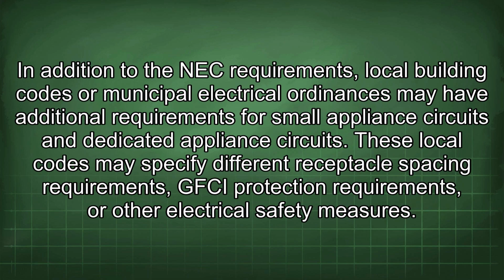In addition to the NEC requirements, local building codes or municipal electrical ordinances may have additional requirements for small appliance circuits and dedicated appliance circuits. These local codes may specify different receptacle spacing requirements, GFCI protection requirements, or other electrical safety measures.